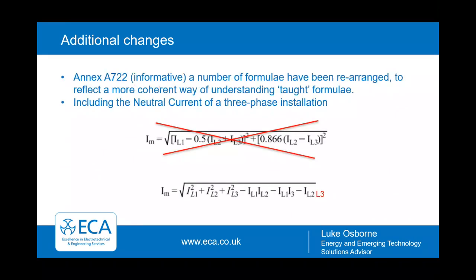There's another additional change. There's been a tidying up of the formula to reflect a 'taught' formula more, as you can see on your screen from Annex A722. This is for the neutral current of a three-phase installation. You may note on the bottom there, the L3 at the end, I've circled that there. If you've downloaded Amendment 1, that L3 is missing from that equation. So the equation actually didn't make much sense without that. That again will be amended in the corrigendum coming through. It makes the equation a lot easier to understand.